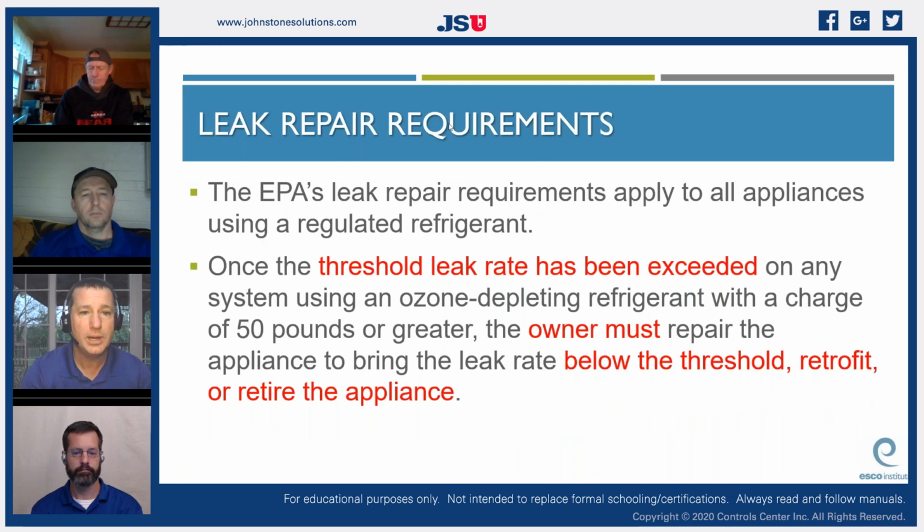Now, if we're talking about leak rates, EPA leak repair requirements apply to all appliances using a regulated refrigerant. So any chlorinated or fluorinated refrigerant. Once the threshold leak rate has been exceeded, remember that's your 10%, 20%, or 30%, on any system using an ozone depleting refrigerant with a charge of 50 pounds or greater, that's our key, 50 pounds, the owner must repair the appliance to bring the leak rate below the threshold, retrofit, or retire the appliance.